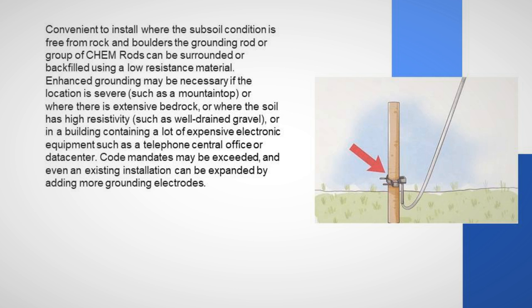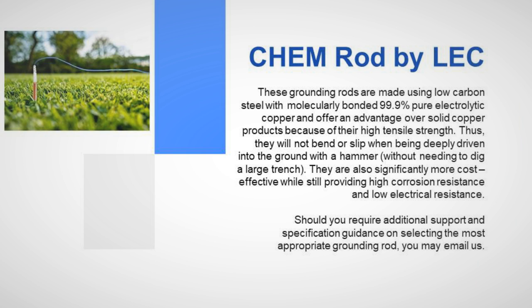Enhanced grounding may be necessary if the location is severe, such as a mountaintop or an area with extensive bedrock, or where the soil has high resistivity, such as well-drained gravel, or in a building containing a lot of expensive electronic equipment such as a telephone central office or data center. Code mandates may be exceeded, and even an existing installation can be expanded by adding more grounding electrodes.